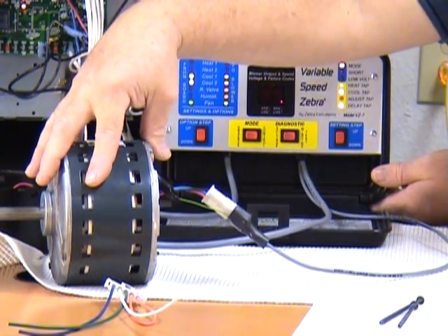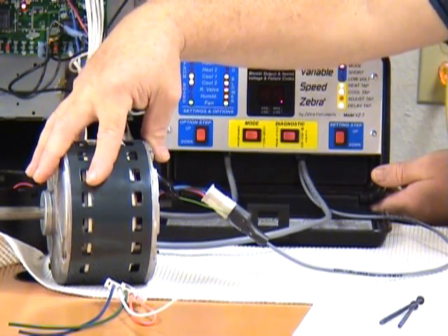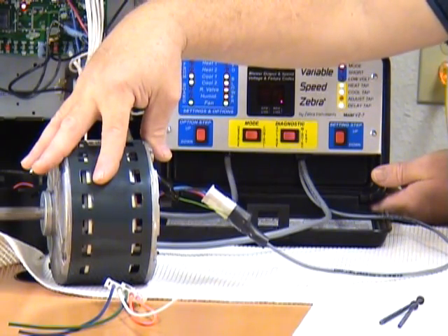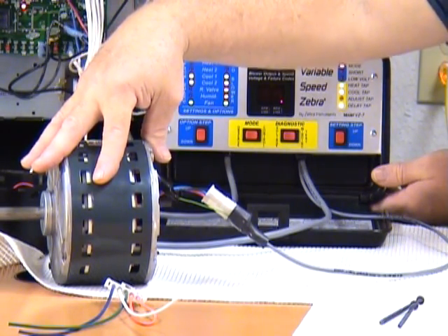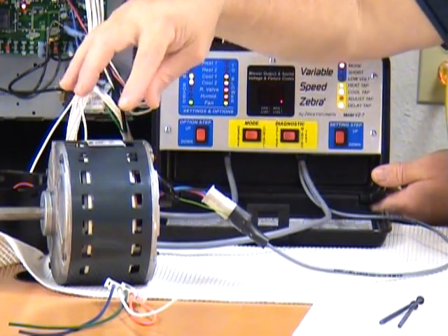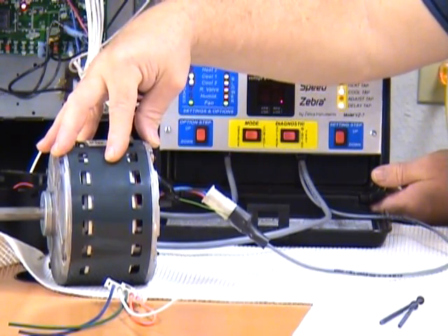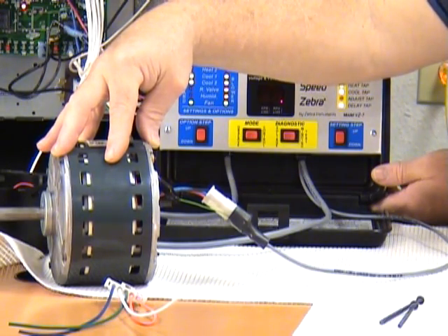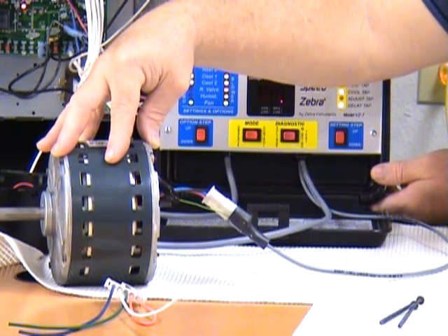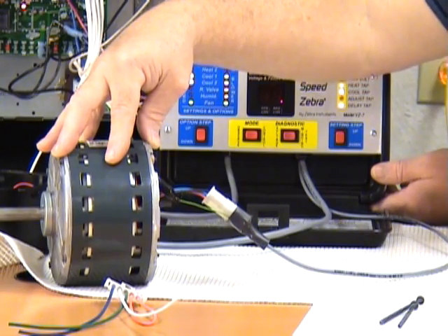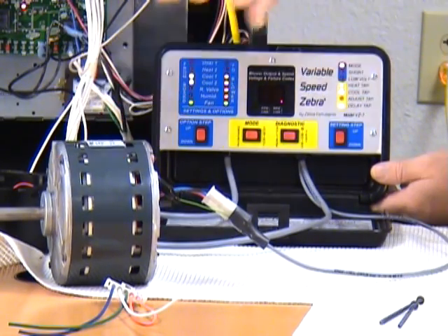This is a motor with permanent magnets in it that actually generates voltage when you turn it. It's just like a DC motor. So when you spin that shaft, you're generating a voltage in there that we use to do a number of tests. It performs about 15 or 20 different tests that, for the most part, you could perform with a voltmeter, ohm meter, but it makes it a lot simpler.